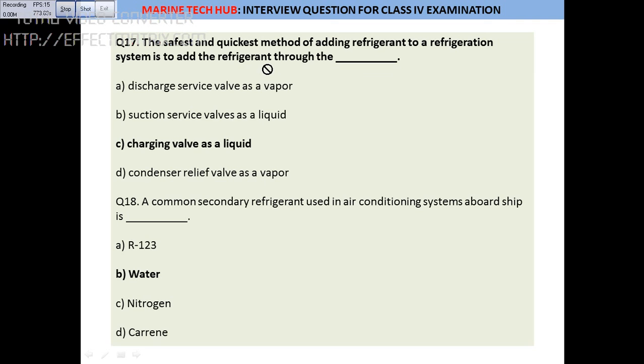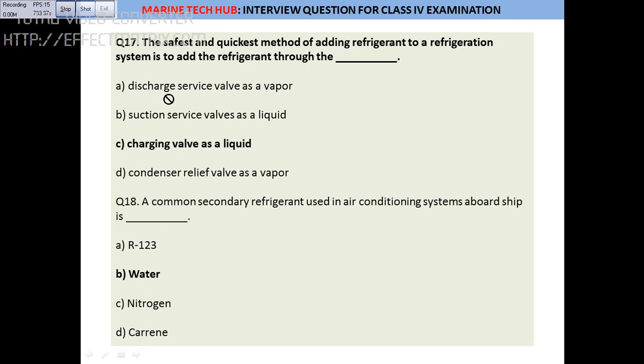Question 17: The safe and quick method of adding refrigerant to the system is to add liquid, not vapor — vapor takes a lot of time. When charging, make sure the charging valve is positioned after the condenser on the liquid line. Do not charge on the suction or discharge side of the compressor.